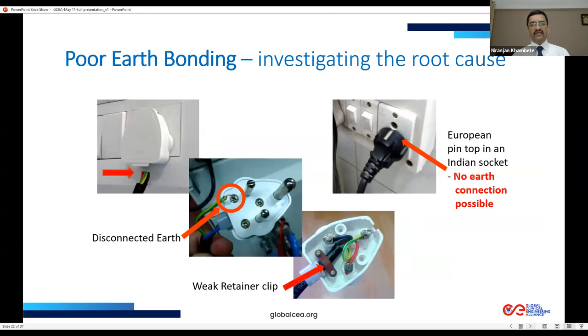As a clinical engineer on the field, when we experience these scenarios, it's good to analyze where things are going wrong. Having seen the use of these 3-pin plugs, I've seen the wires get pulled out, the earth gets disconnected, but the phase and neutral remain connected. So it's not possible to visually identify that the earth is disconnected, nor does the equipment stop working, because phase and neutral are still supplying power.